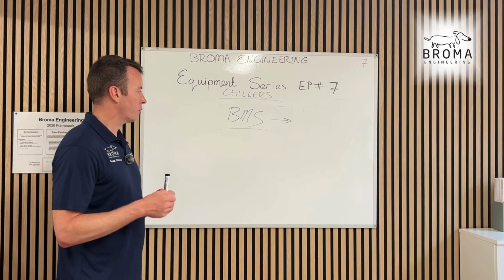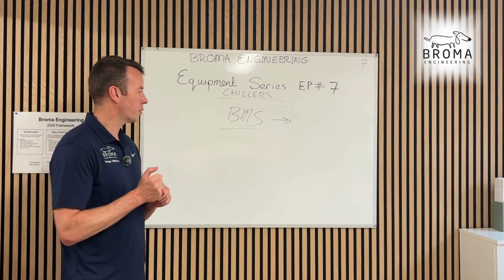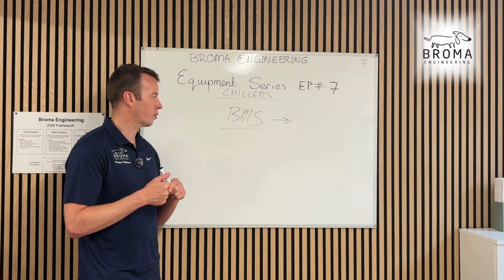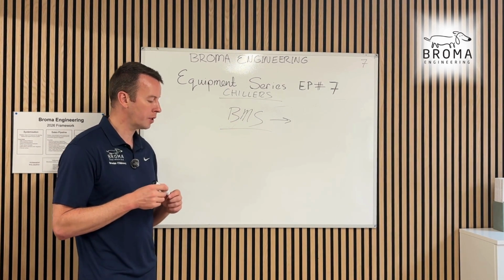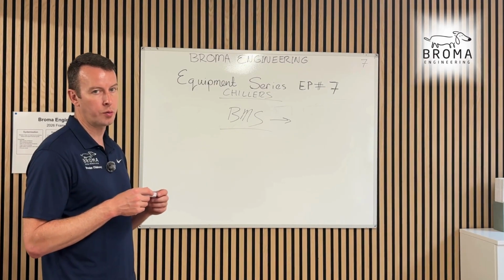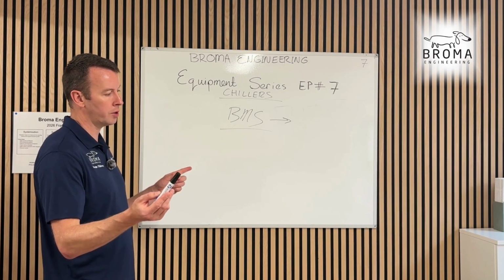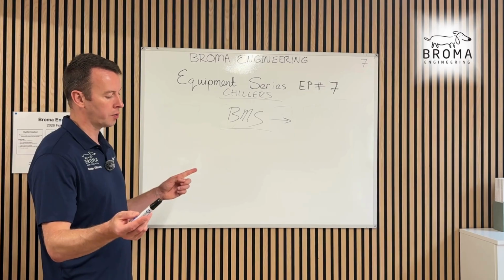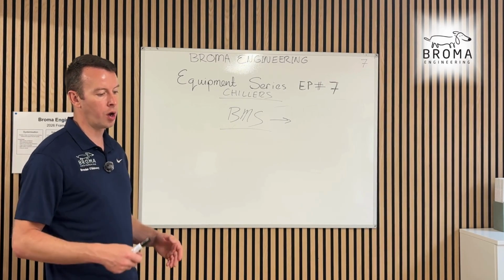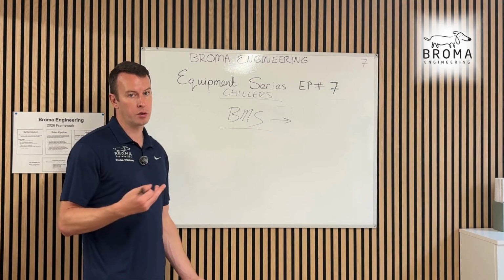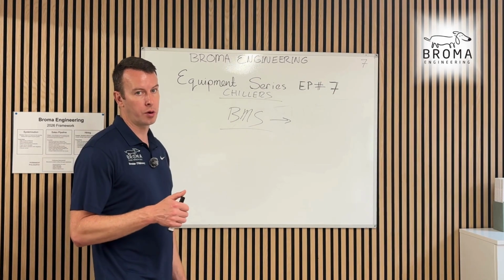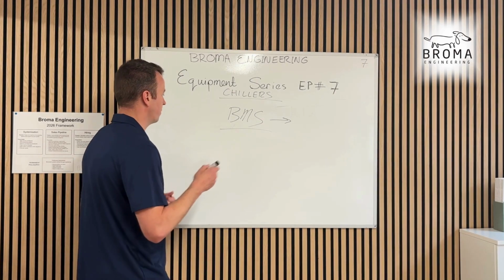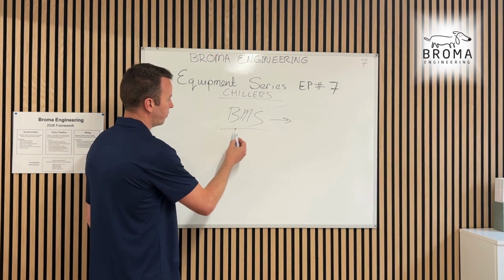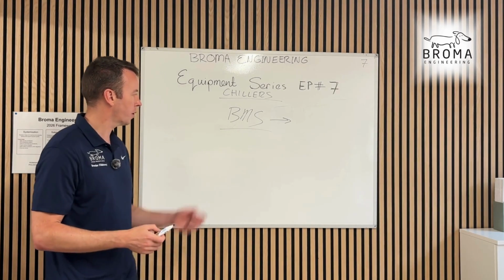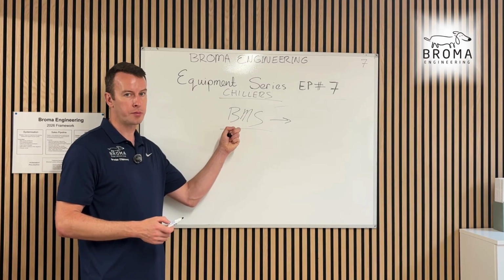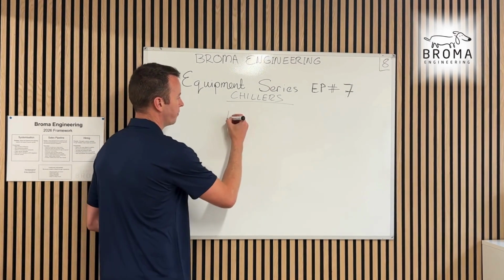Driving the schedule every morning with project controls, making sure we understand what's done, what's not done. We'll talk about a detailed schedule in another video, but that's how we measure it - a percentage completion based on all the little tasks. We don't just have big, massive tasks that go on for a week; the longest task possible is a day. That's how we do a micro schedule for a chiller - day-tight compartments. I won't talk too much more about BMS, but that has to be done for your yellow tag. So the next step is power on.